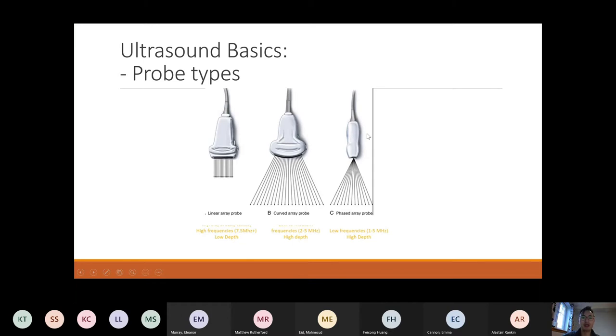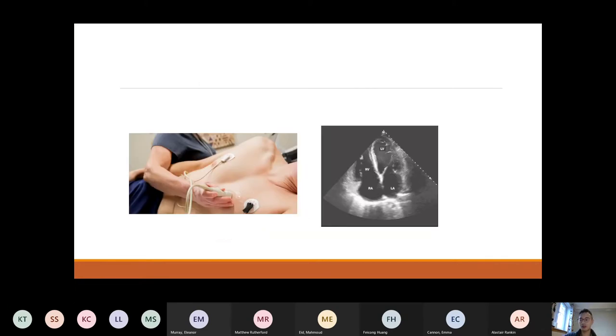This image, I took online for a purpose, because it very nicely demonstrates that the phase array emits the ultrasound through a pinhole. Because of its small probe and small emission window, it allows it to see through small gaps, such as between your ribs. It's for that reason the phase array probe is used in echocardiograms.